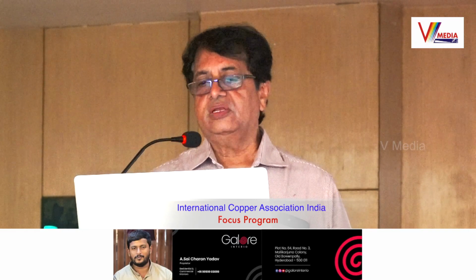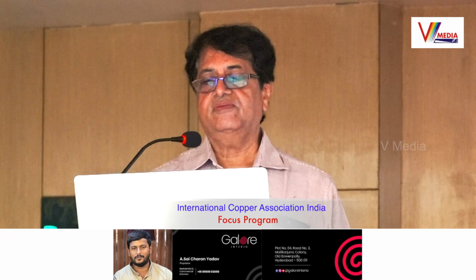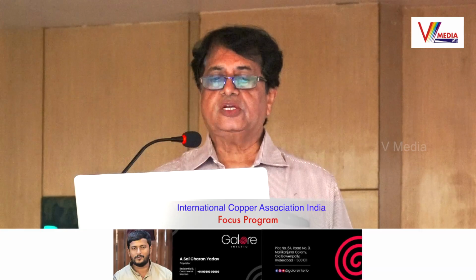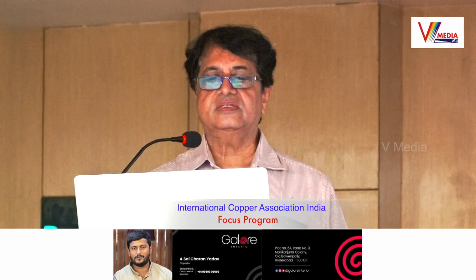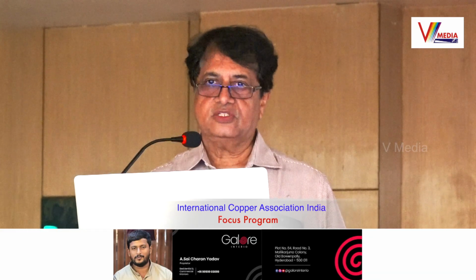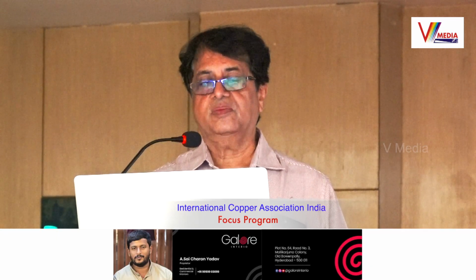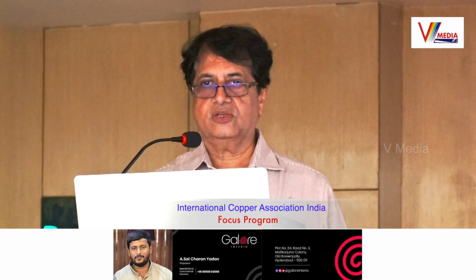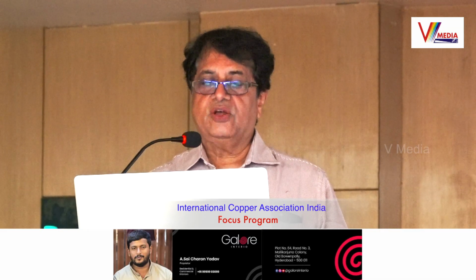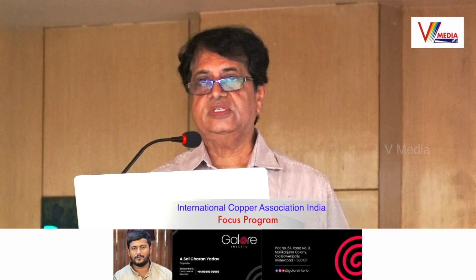Different clearances have been mentioned in the regulations depending on the voltage level of the electrical line, whether it is a low tension line, 11 kV line or higher, or EHV line. In respect of EHV lines especially, certain clearances are required apart from the horizontal and vertical clearances. Certain clearances are required below the line, that is called a right of way. It is mandatory to maintain these clearances for the owner of that line to carry out electrical maintenance, or maybe because of some augmentation which they have to carry out in the future. So this right of way is one of the important requirements which generally is not seen to be maintained properly.